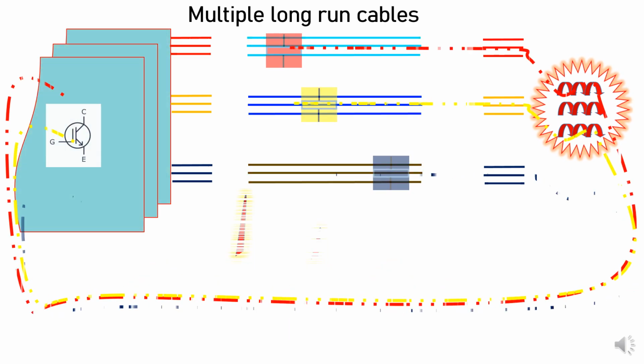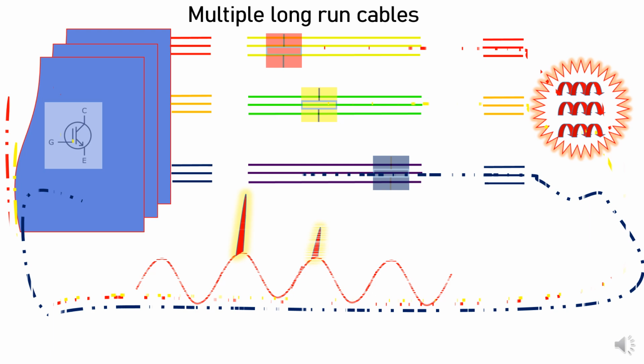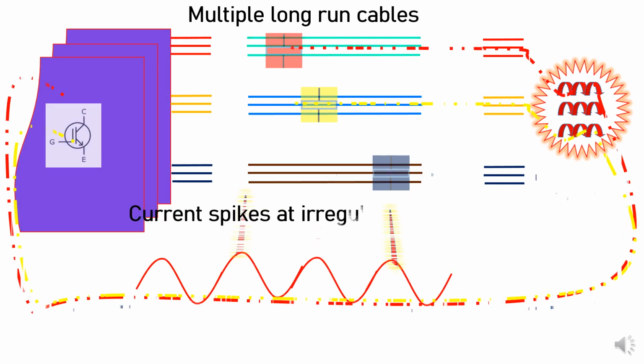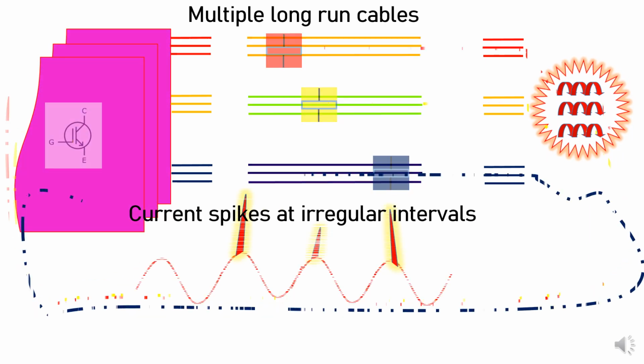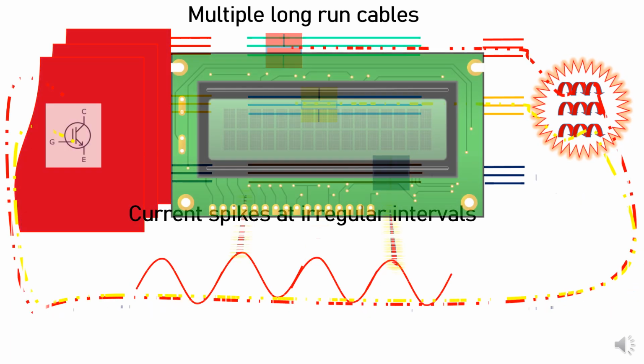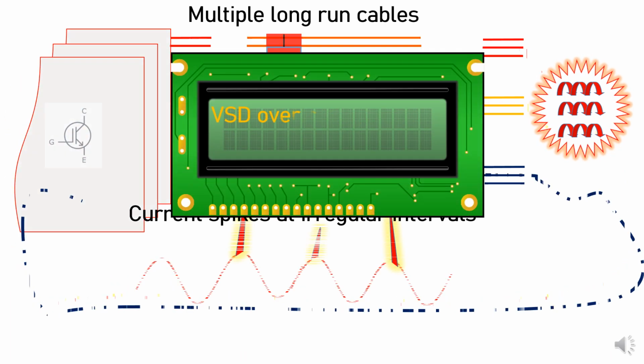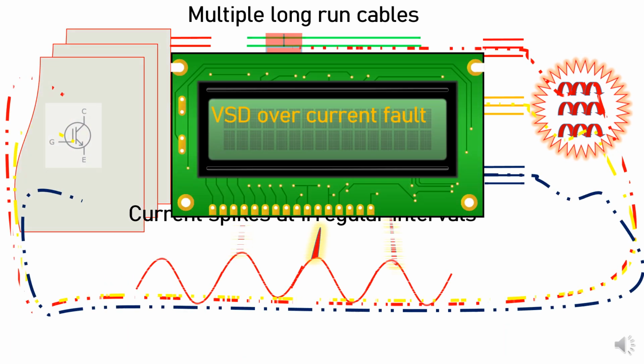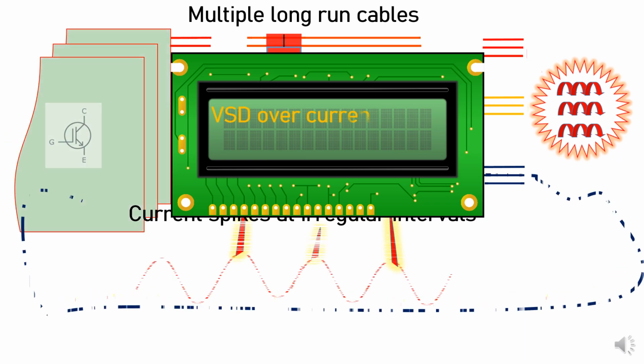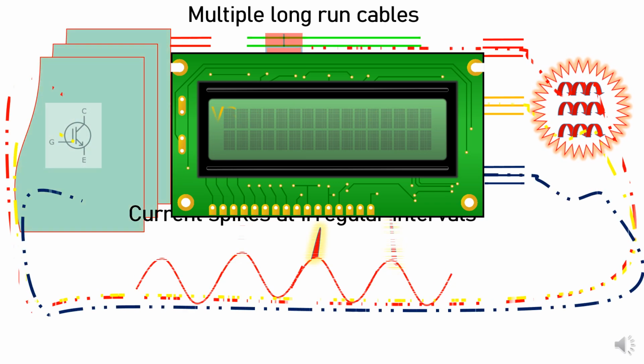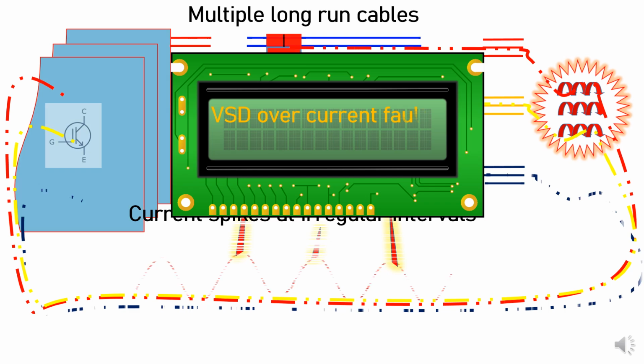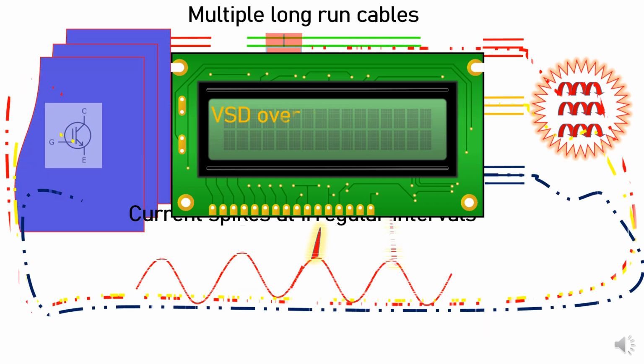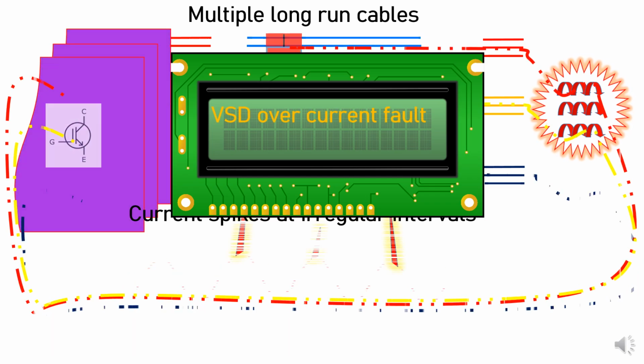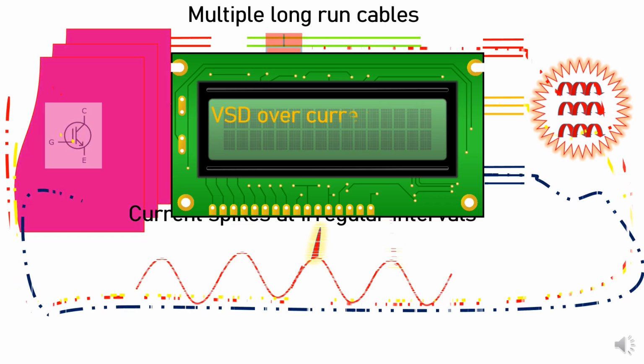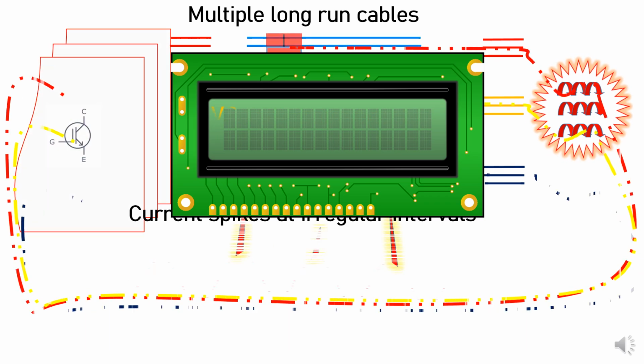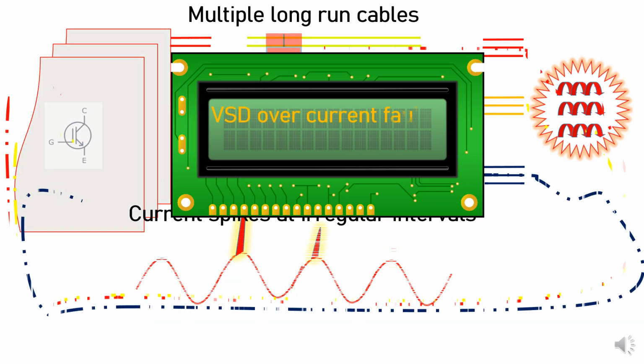There are spikes being observed in the current supplied by the inverter, and one beautiful day once it touches the overcurrent limit of the inverter, our inverter will trip on VSD overcurrent fault. We will not find anything wrong at the VSD end as well as the cable as well as the motor. Once we reset this particular fault, it will run for a certain time period, and one beautiful day again it trips. So this is the second headache for the user. Unwanted overcurrent fault will be observed by the VSD inverter.